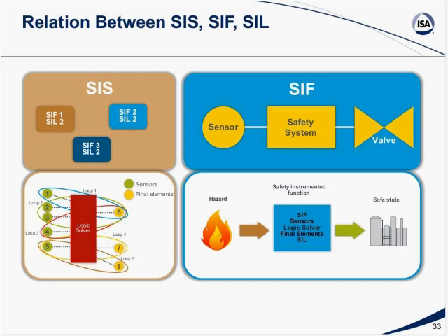So if you look at this diagram, you'll see that a SIS will contain multiple SIFs, and each SIF would have a separate SIL level. So this is one safety instrumented system on the left, and you have multiple SIFs that are identified, multiple safety instrumented functions, and each SIF would obviously have a safety system, a sensor, and a valve, and that sensor, safety system, and valve would have a particular SIL rating. And then you would identify multiple SIFs like those, where each of them would have a separate SIL rating. So you could very well have a complete safety instrumented system with 3 different systems with a SIL 1, SIL 2, and a SIL 3 level. So it's very, very important to understand that a SIL level actually is not assigned just to the safety system, but it includes the sensors, the final control elements, and the PLC, or the programmable electronic system, or the programmable controller, whatever you would like to call it.